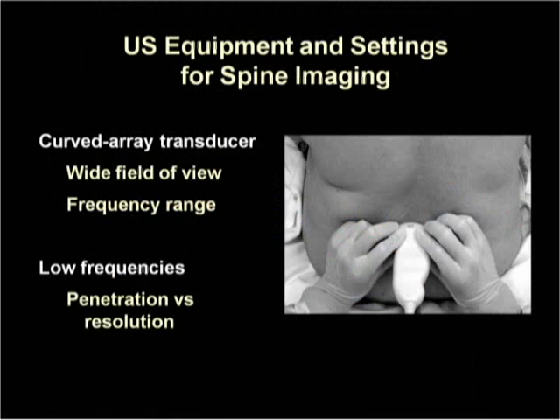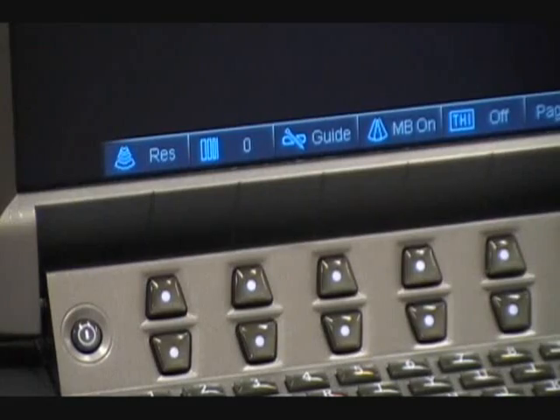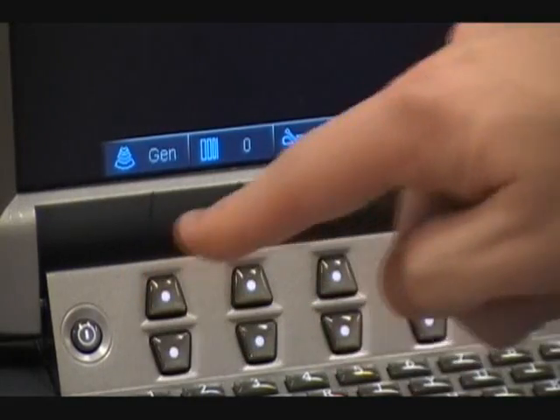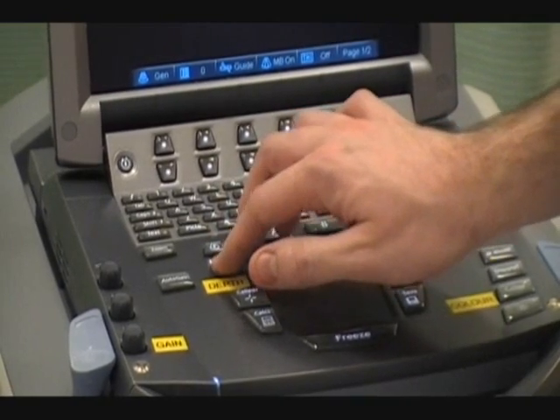A low-frequency, curved-array ultrasound probe is recommended for scanning the adult lumbar spine, particularly in obese patients. The structures of interest are located deep to the skin and low frequencies are necessary for adequate penetration. The wide field of view of a curved array facilitates recognition of the anatomy. The frequency of the probe should be set to the low range and the focus and depth also set appropriately. An initial depth setting of at least 6 cm is usually required.